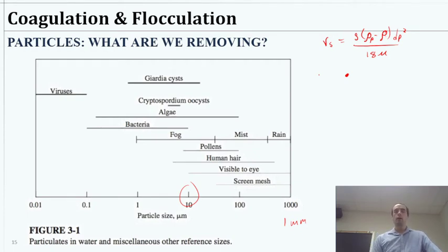Small caveat, something called ballast. I'll talk about it a little bit in a few minutes. It's essentially when you're doing the coagulation, sometimes you add actual sand that's presumably going to get caught up with these larger particles. That could make it more dense, a cheap and easy way to make them more dense. Sometimes we do that. But even that, maybe not the best solution compared to the impact if you change the diameter of the particles.